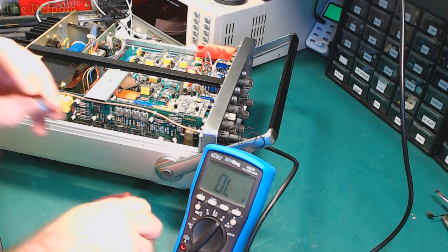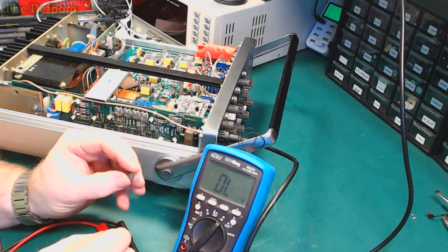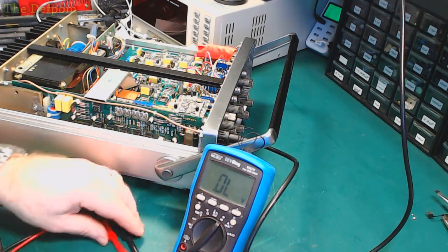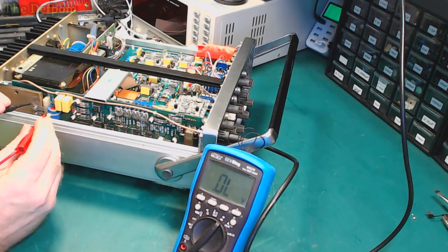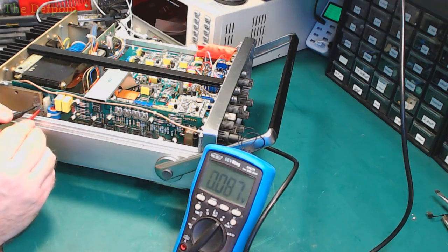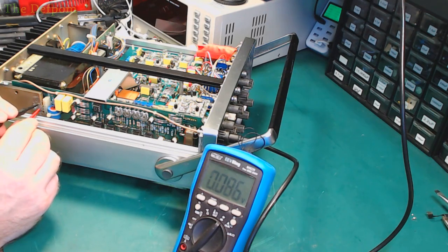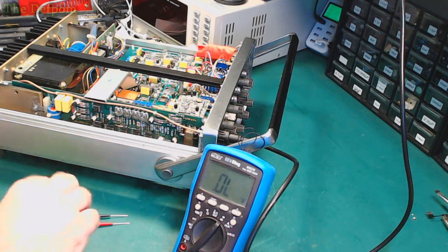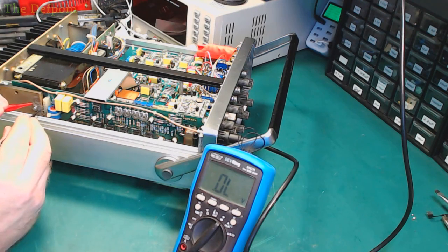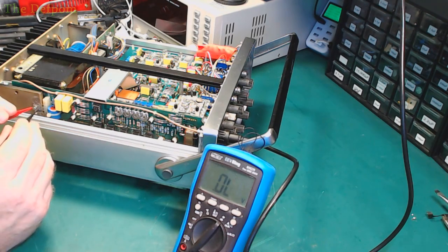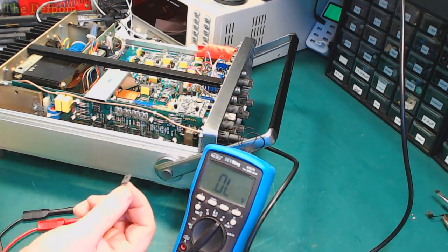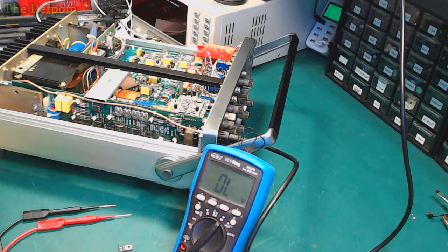So whatever's controlling this device seems like it might have a problem. This isn't the problem. Measure across there, should be able to verify that. 0.086, it's the same. If I reverse the leads, let's make sure they're both reversed, just in case the polarity matters. No, it doesn't matter. So whatever's controlling this device looks like it's got a problem. Okay, well that means I'd have to replace it at least.